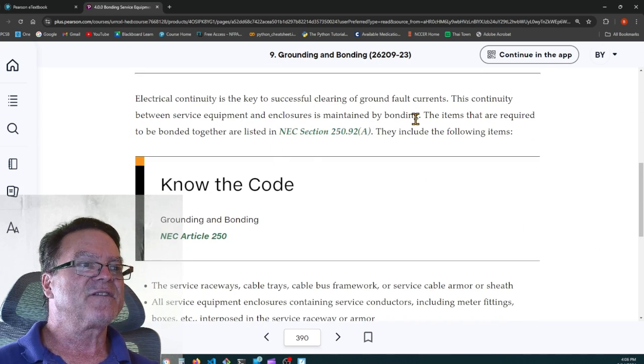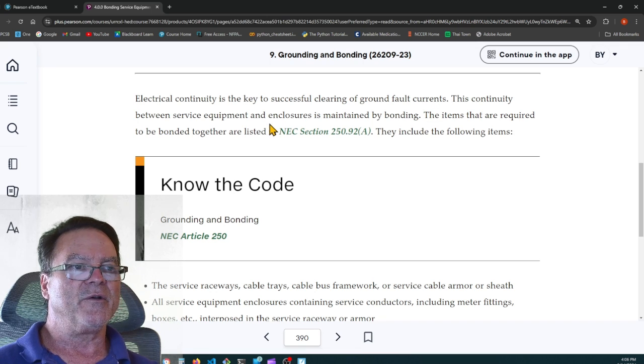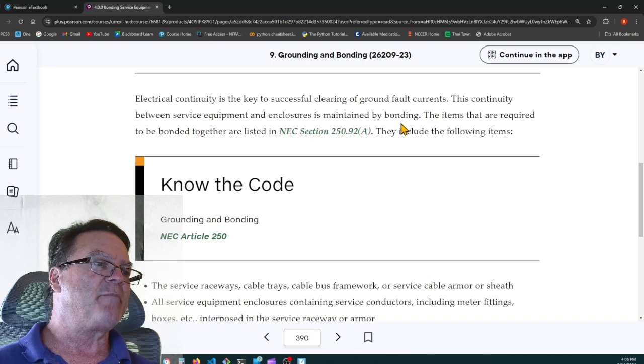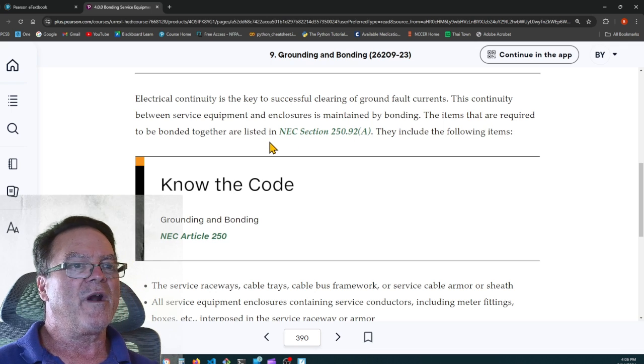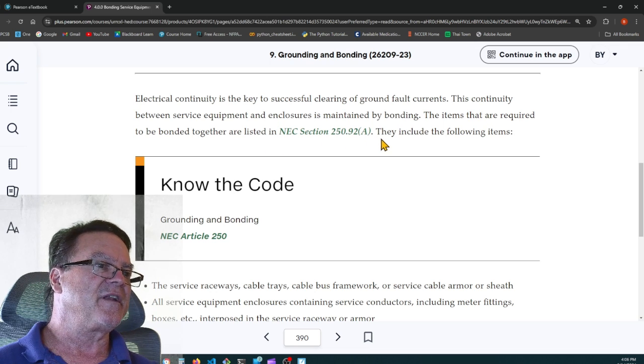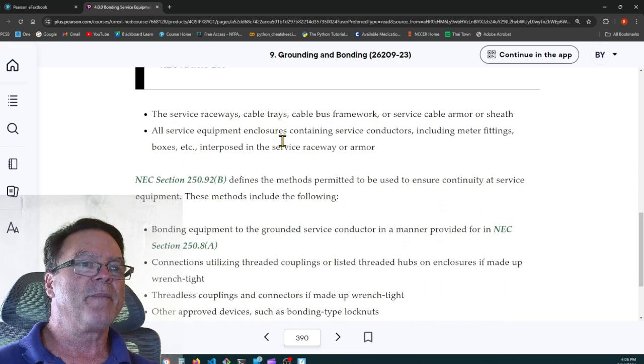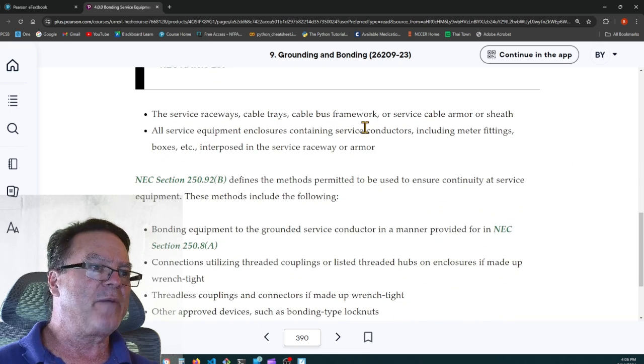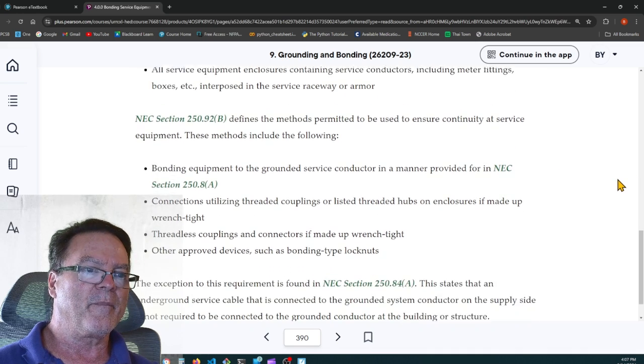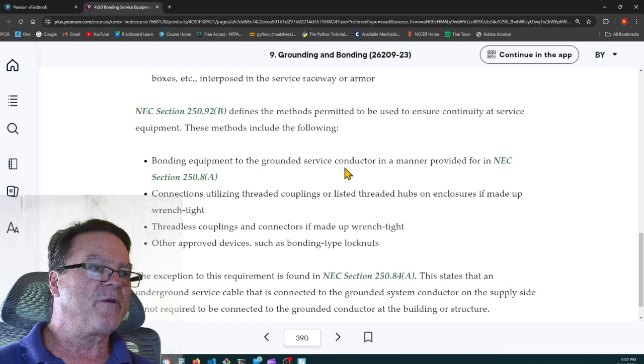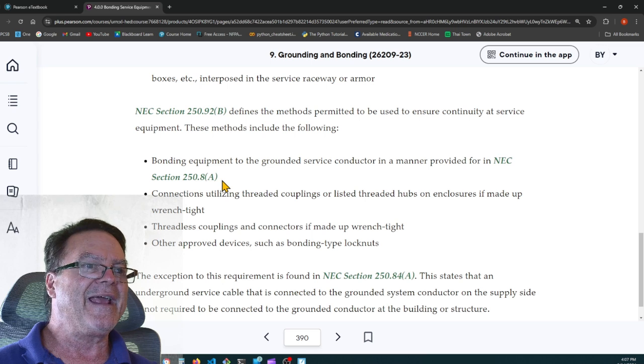Electrical continuity is the key to successful clearing of ground fault currents. This continuity between service equipment and enclosures is maintained by bonding. The items that are required to be bonded together are listed in NEC section 250.92A. They include the following items: service raceways, cable trays, cable bus framework, or service cable armor or sheath. All service equipment enclosures containing service conductors, including meter fittings, boxes, etc., interposed with the service raceway or armor. Bonding equipment to the grounded service conductor in a manner provided for in NEC section 250.8.